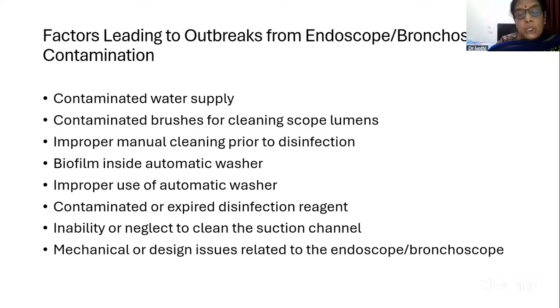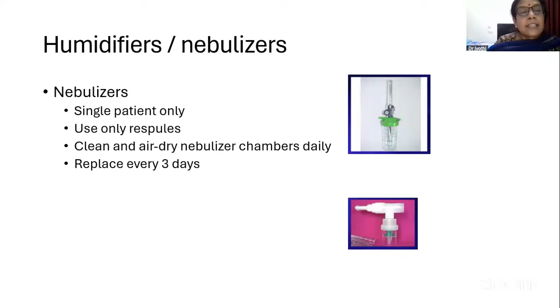So biofilm inside the automatic washer, improper use of the automatic washer, contaminated or expired disinfection reagent, inability or neglect to clean the suction channel, mechanical or design issues related to the endoscope or bronchoscope. And humidifiers and nebulizers: single patient only, use only respules, then clean and air dry nebulizer chambers daily and replace every 3 days.